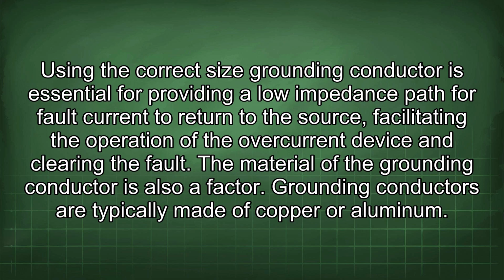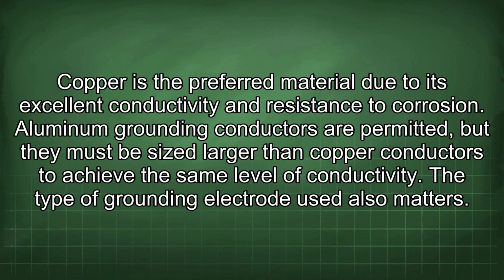The material of the grounding conductor is also a factor. Grounding conductors are typically made of copper or aluminum. Copper is the preferred material due to its excellent conductivity and resistance to corrosion. Aluminum grounding conductors are permitted, but they must be sized larger than copper conductors to achieve the same level of conductivity. The type of grounding electrode used also matters.